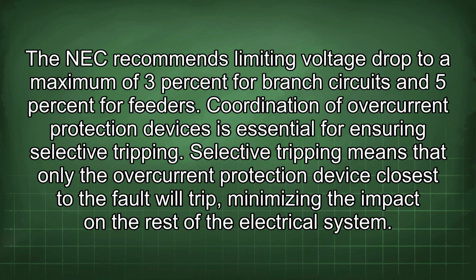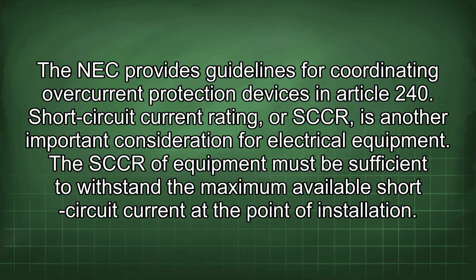Coordination of overcurrent protection devices is essential for ensuring selective tripping. Selective tripping means that only the overcurrent protection device closest to the fault will trip, minimizing the impact on the rest of the electrical system. The NEC provides guidelines for coordinating overcurrent protection devices in Article 240.